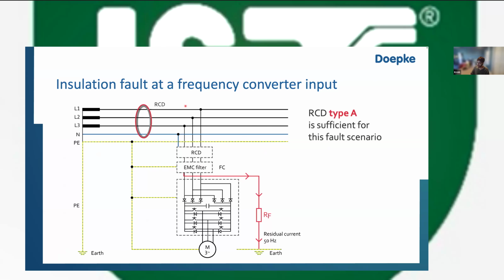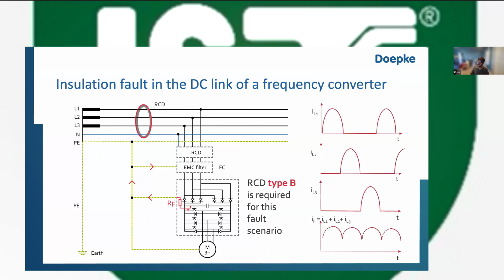Now, if we talk specifically about the case of an elevator, if the fault happens before the VFD, then you're just going to get 50 hertz. A type A is sufficient in these cases, right? However, if you have a fault that occurs in the DC bus, then a type B is required. Why? Again, like I said, during the first phase's half cycle, you get a peak, then nothing. Second phase, the peak is offset by 120 degrees. Third phase, it is offset by 240. Resultant is peak, peak, peak, peak over a certain smooth piece. And only the type B RCD can interrupt a situation like that.